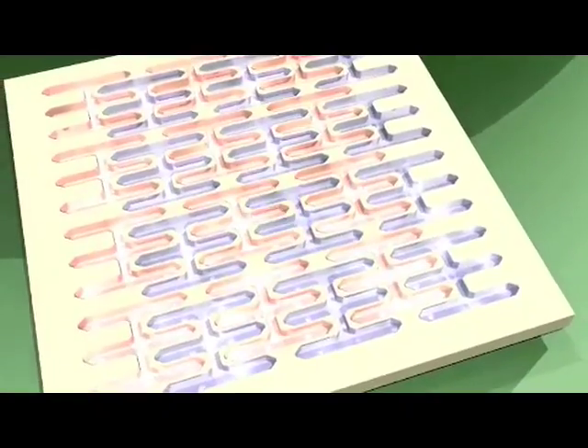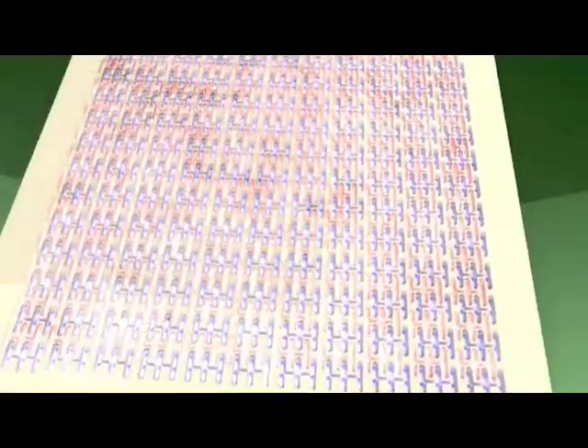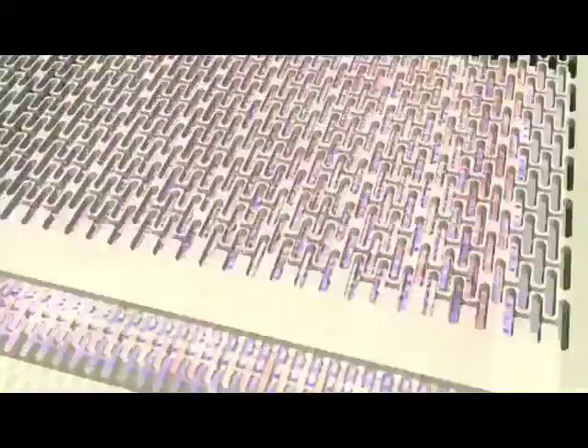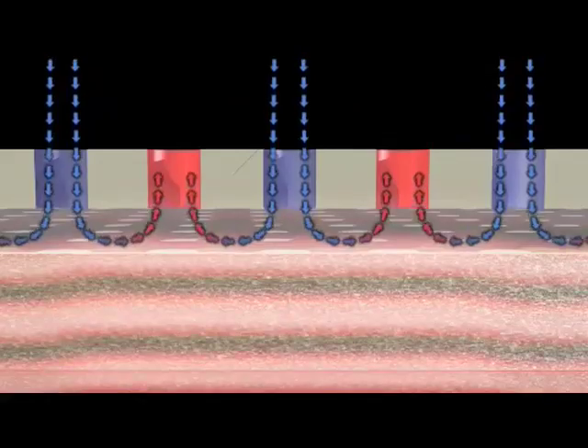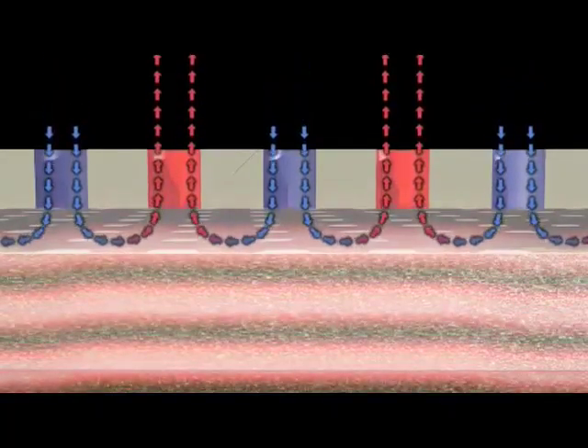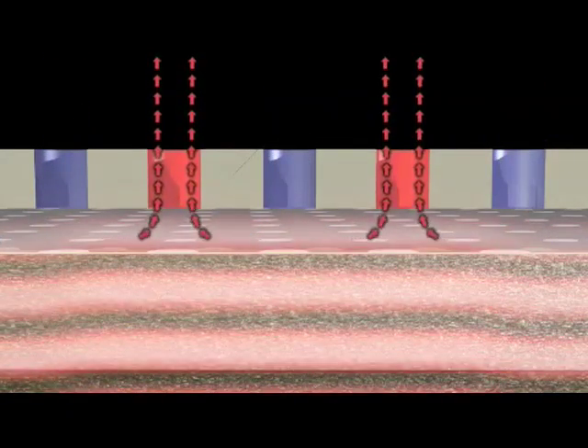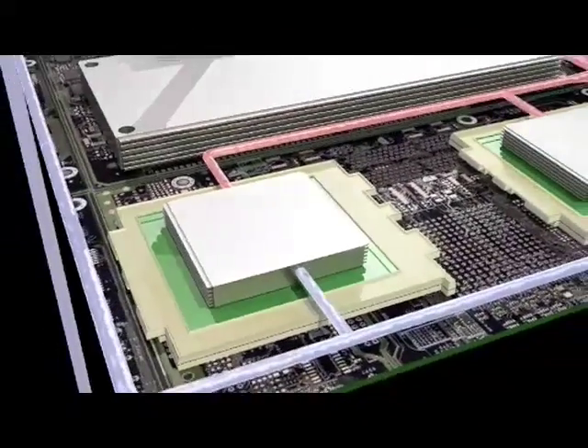Delivering on its name, Aquasar will use water instead of air as its coolant to capture and transport the heat. Water is both 4,000 times more efficient than air and has superior heat transporting properties. Using powerful chip-level water coolers, the distilled water does not need to be chilled to low temperatures and can be kept at about 60 degrees Celsius to cool the chips below the maximally allowed 85 degrees Celsius.